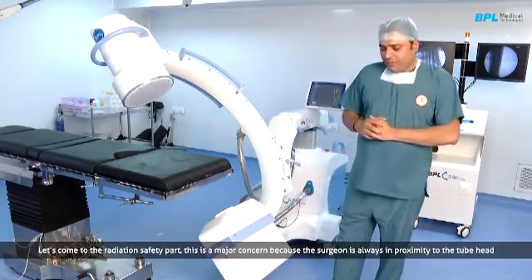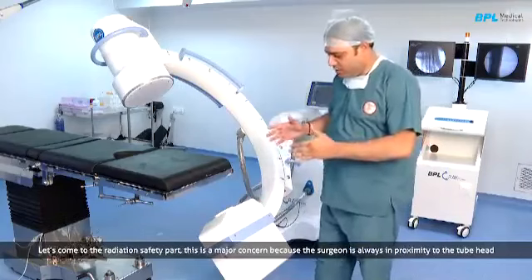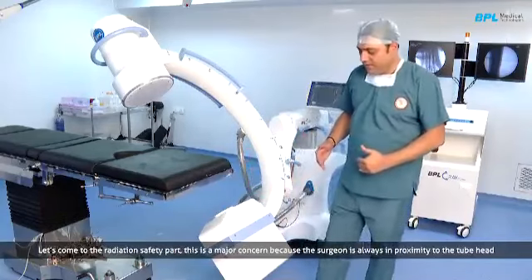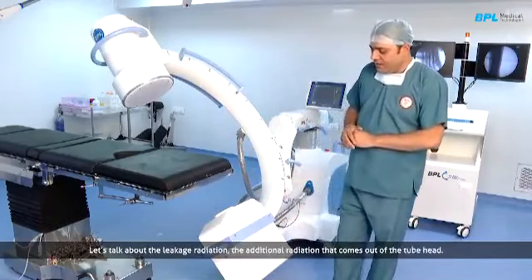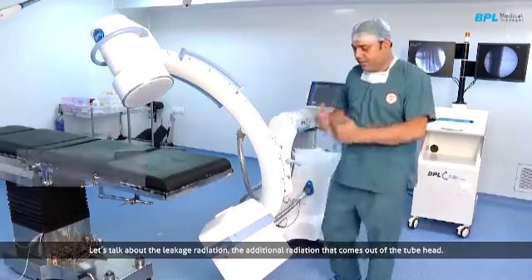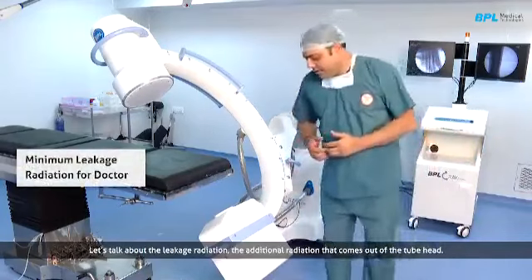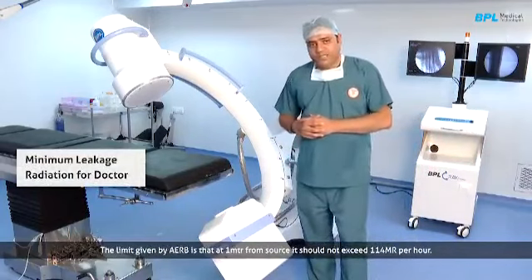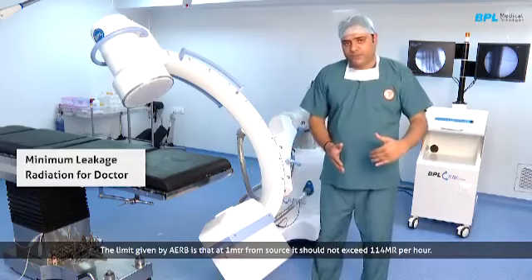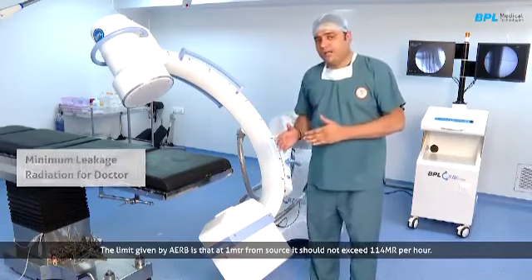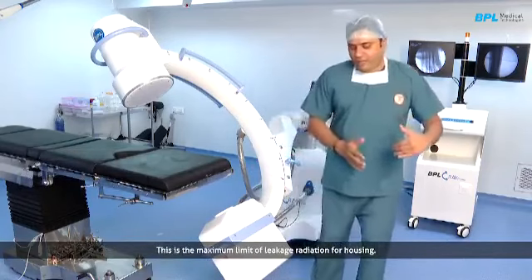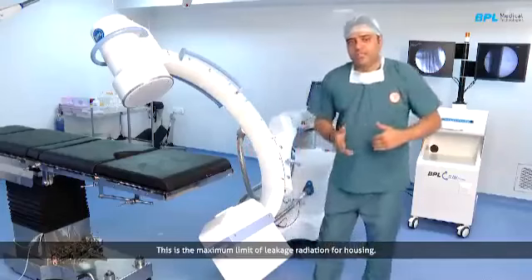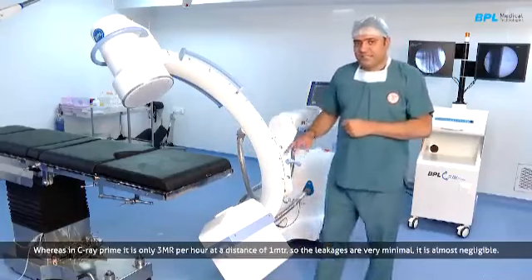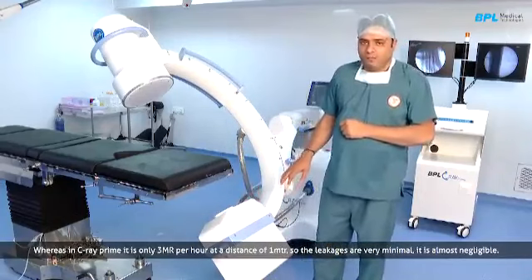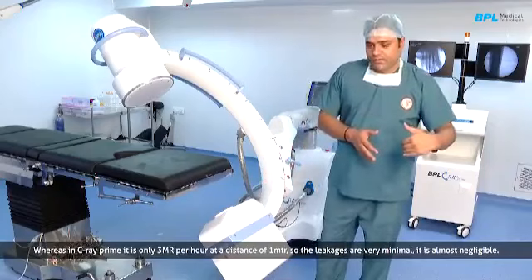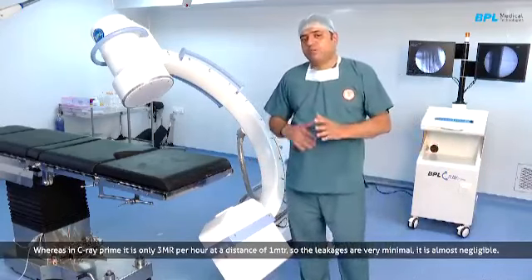Now let's come to the radiation safety part, and this is a major concern, because surgeon is always in the proximity of tube head. He's the closest person to the tube head. And let's talk about the leakage radiation, the radiation which comes out from the leakage. The limit given by AERB is that at 1 meter from source it should not exceed 114 mR per hour. 114 mR per hour at a distance of 1 meter from source is the maximum limit for housing leakage radiation. Whereas in C-Ray Prime, it is only 3 mR per hour at a distance of 1 meter. So you will see the leakage is very minimal, it is almost negligible.